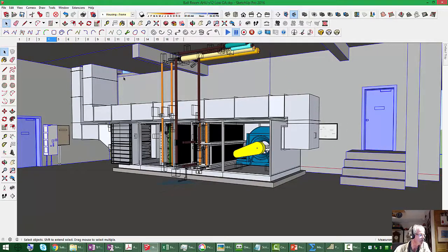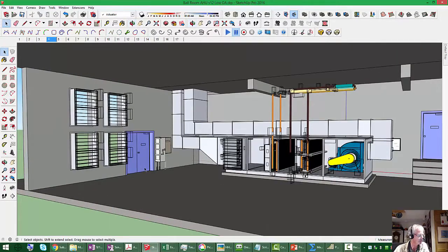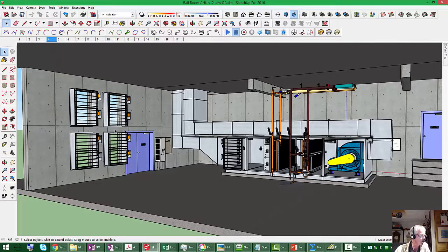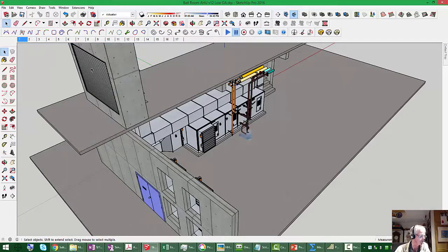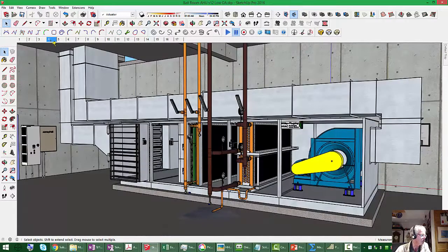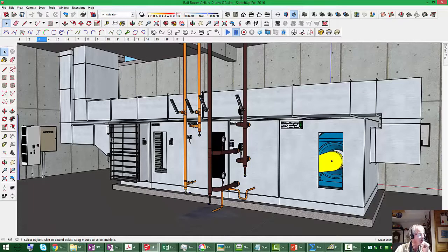In other words, if you step back a little bit more, there's some dampers on the wall that go to the outside. Well, you might think they could be outdoor air intake dampers, and this would make the mechanical room an outdoor air intake plenum. But that kind of doesn't make sense, because if you follow this duct and go back to the overview, that duct goes to this louver, which is also an outside air louver. And if you follow that duct back to the view that we were in a minute ago, it comes into the back end of the unit. I've got the doors open right now. The airflow basically is from this end of the unit towards the supply fan. So that's probably the actual outdoor air connection.